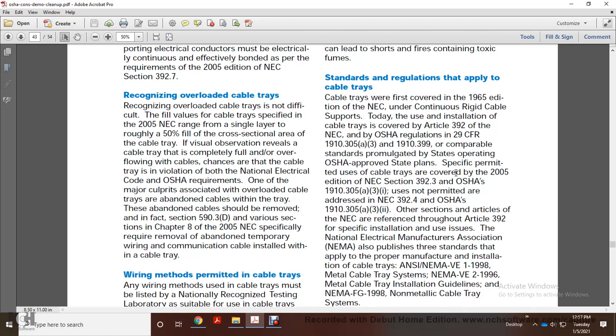Comparable standards are regulated by states operating OSHA-approved state plans. Specifically, permitted use of the cable tray is covered in the 2005 edition of the National Electrical Code 392.3 and OSHA 1910.305(a)(3)(i), and uses not permitted are covered in National Electrical Code 392.4 and OSHA 1910.305(a)(3)(ii). Other sections and articles of the National Electrical Code are referenced throughout Article 392.